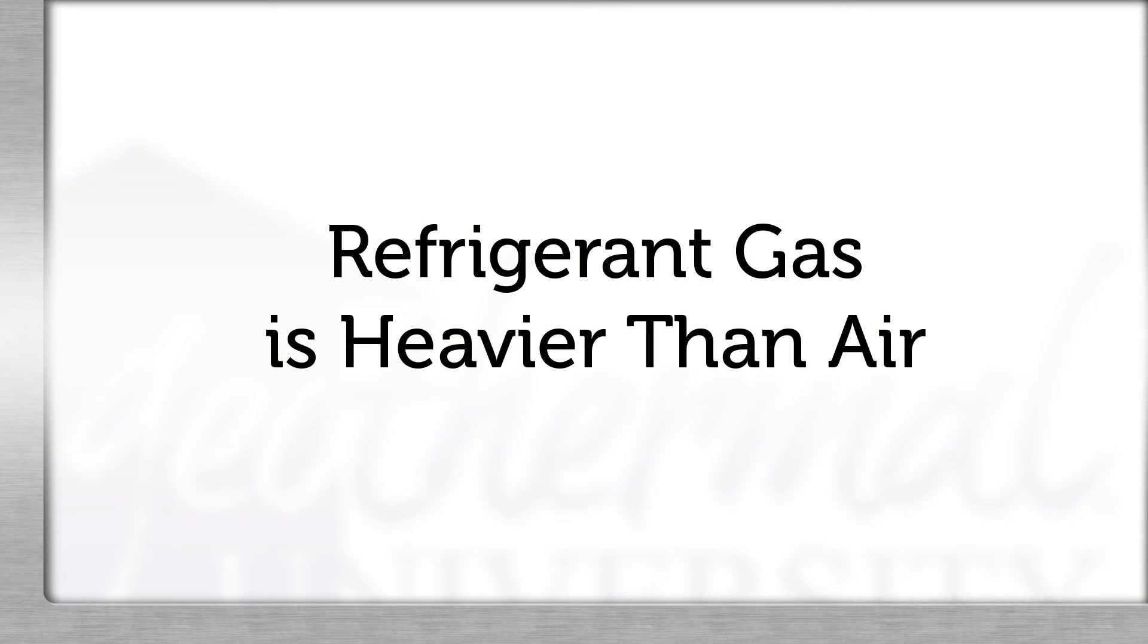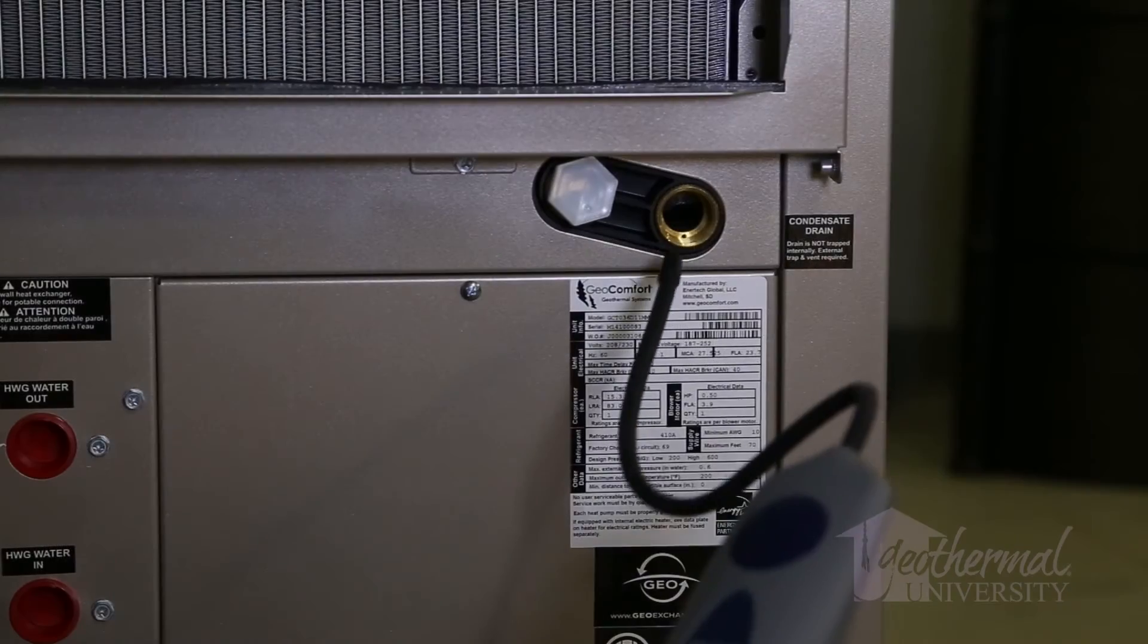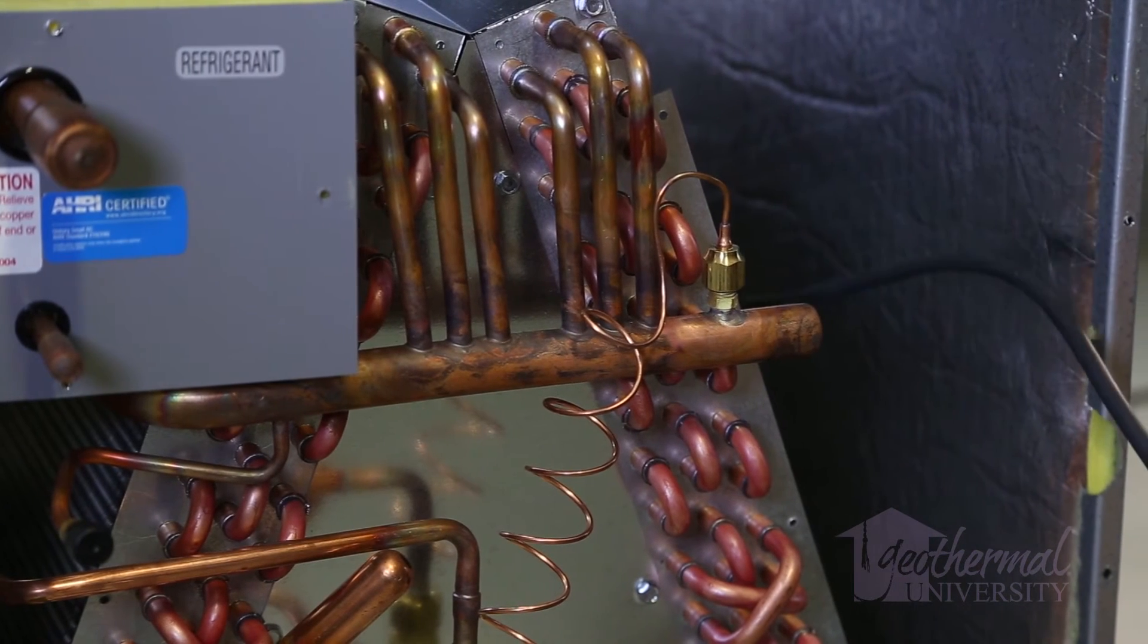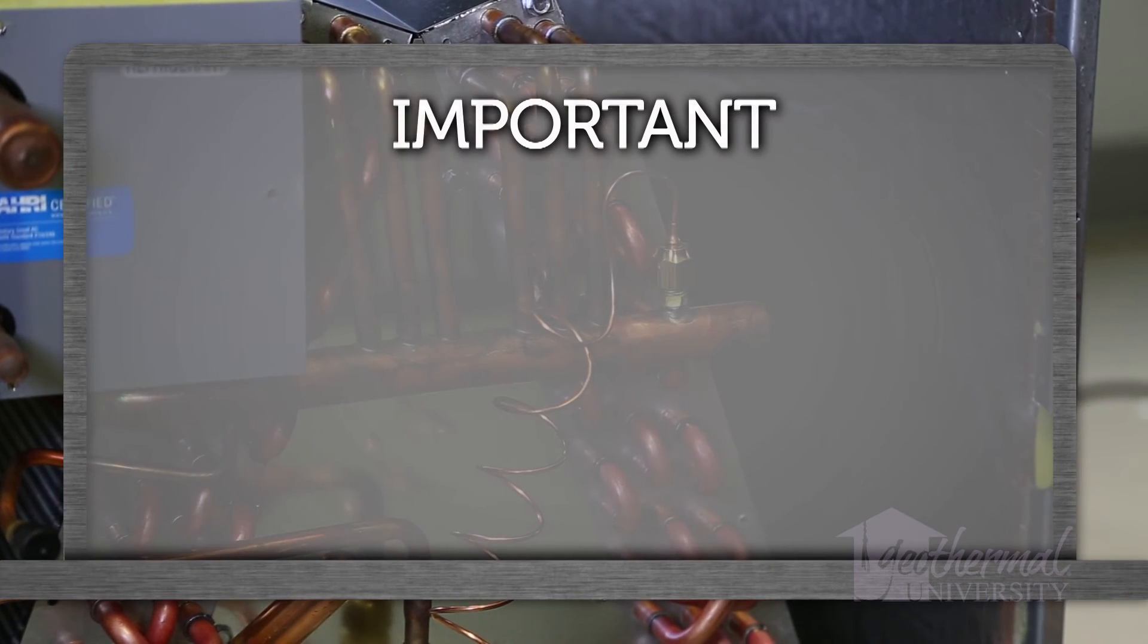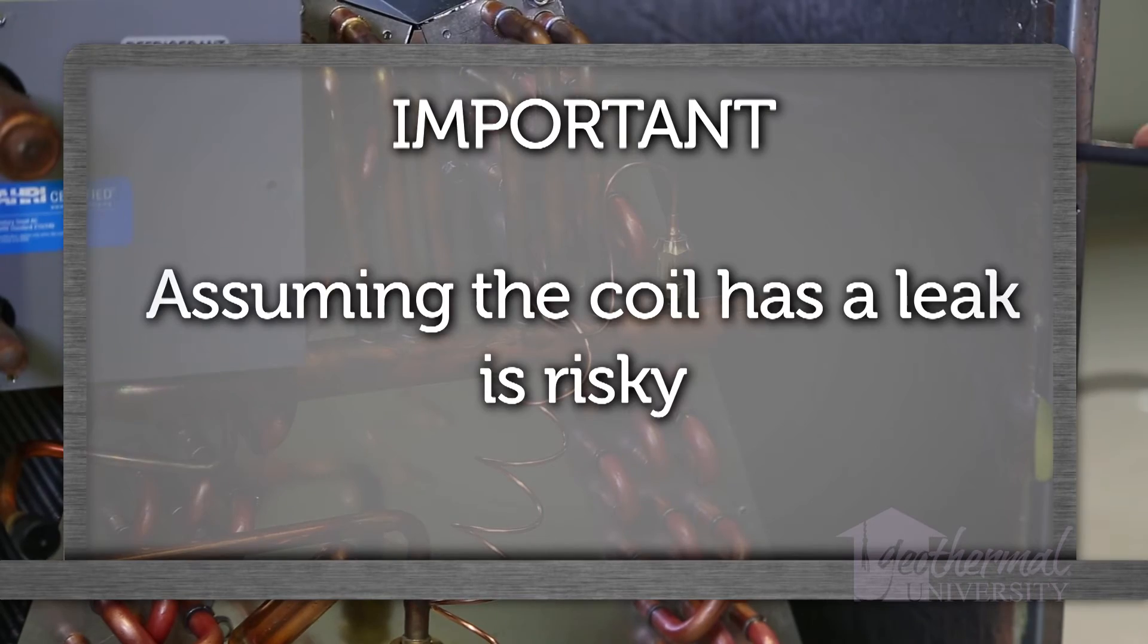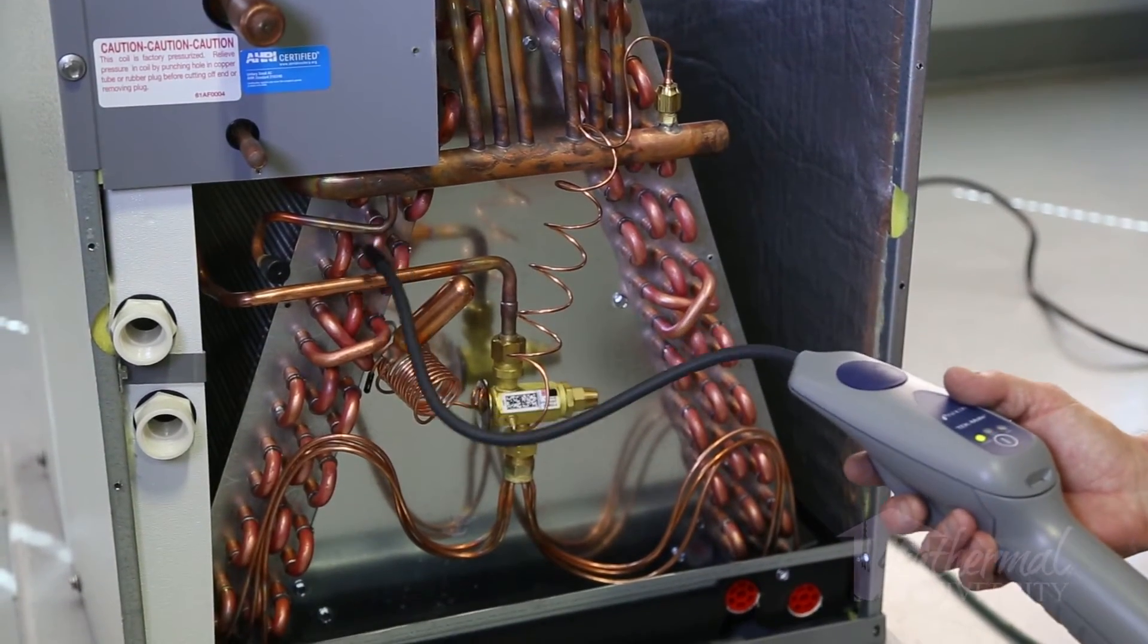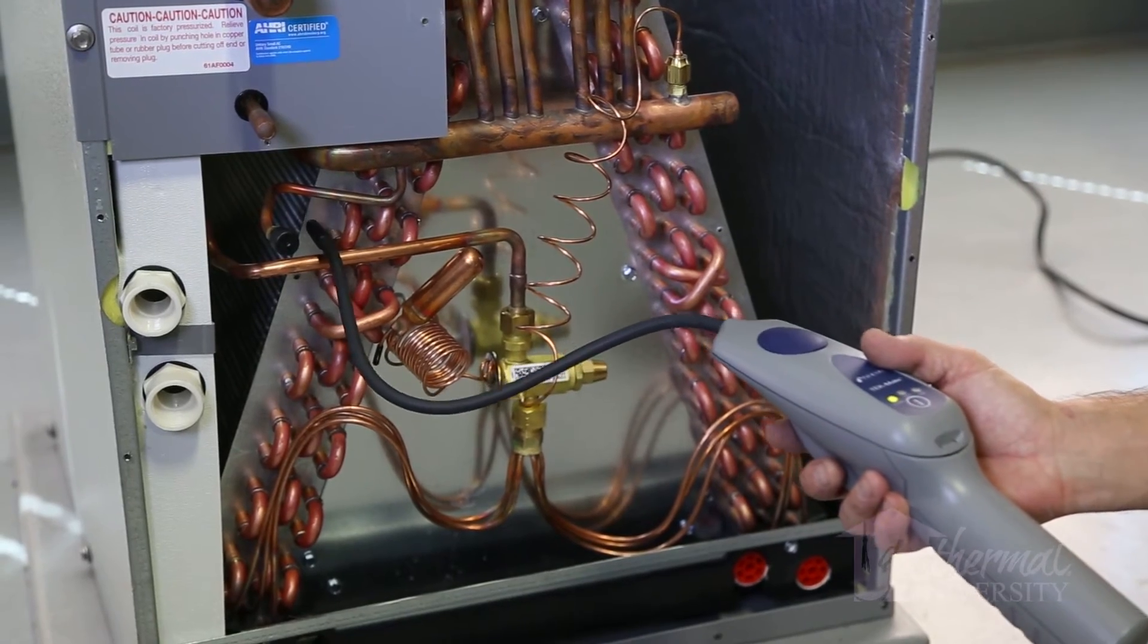Refrigerant gas is heavier than air and gravity will cause the gas to flow to the lowest point. If the evaporator section tests positive, we must expose the entire coil and investigate thoroughly. Assuming or guessing the coil has a leak is risky. A false positive test can lead to a wrong diagnosis and significant expense.